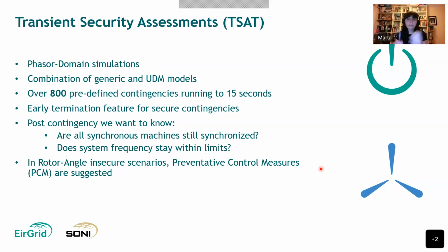What we're interested to know out of this assessment is whether all the synchronous machines are still synchronized, or have we lost some of the units. Also whether the frequency stays within limits in terms of amplitude, the nadir and the zenith, and also the rate of change. In case we have any rotor angle insecurity, if a synchronous unit pole slips, the tool will suggest preventive control actions.